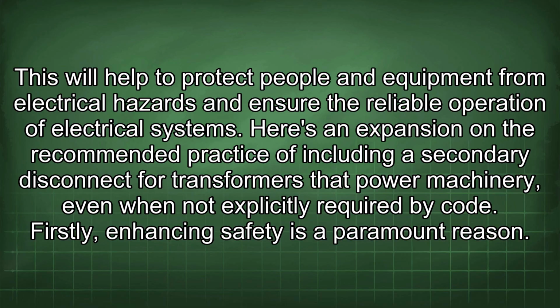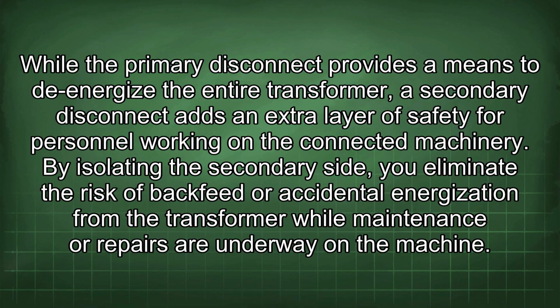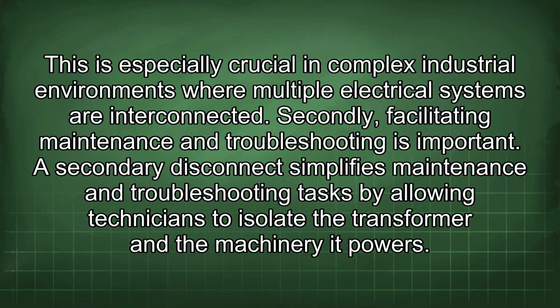Firstly, enhancing safety is a paramount reason. While the primary disconnect provides a means to de-energize the entire transformer, a secondary disconnect adds an extra layer of safety for personnel working on the connected machinery. By isolating the secondary side, you eliminate the risk of backfeed or accidental energization from the transformer while maintenance or repairs are underway on the machine. This is especially crucial in complex industrial environments where multiple electrical systems are interconnected.